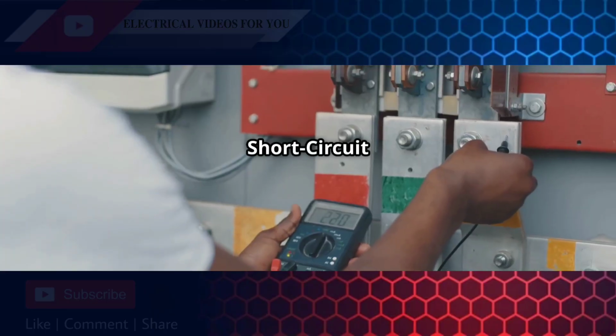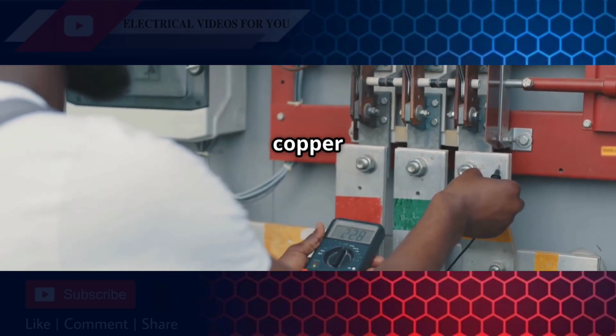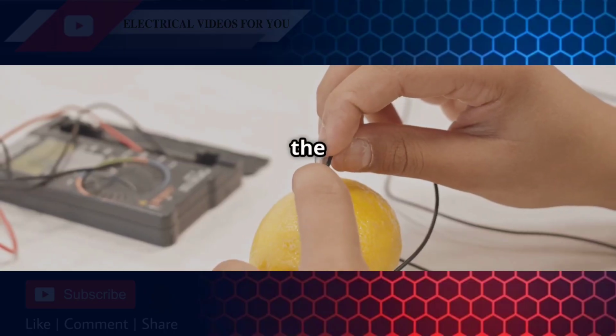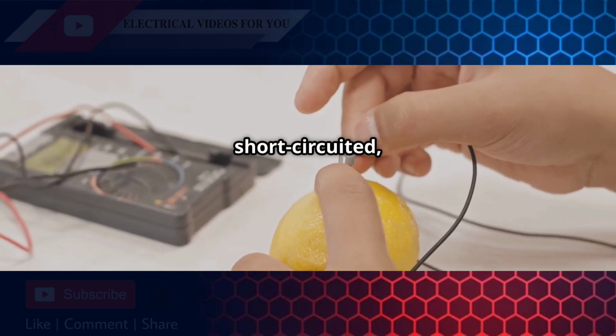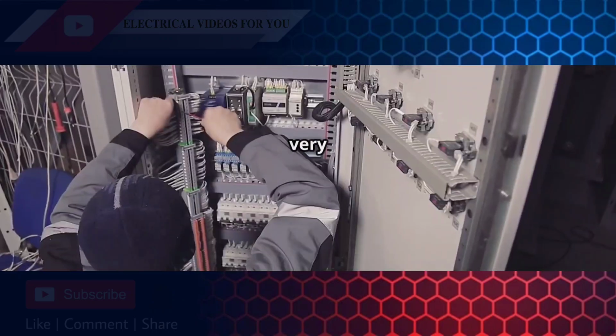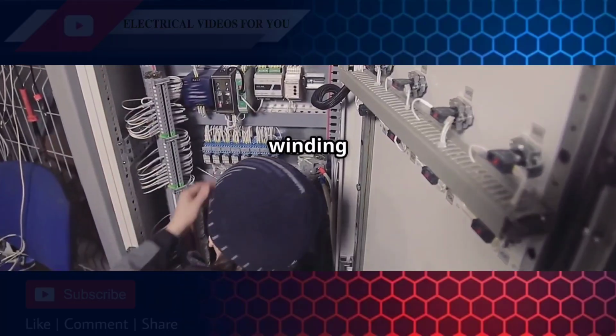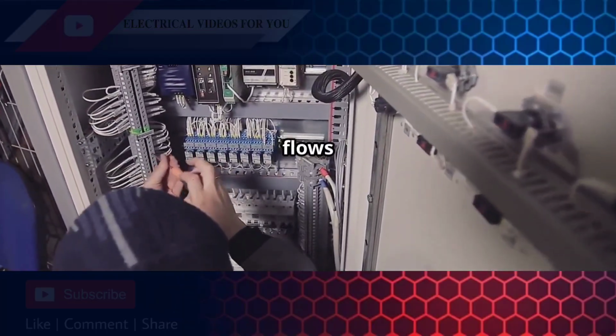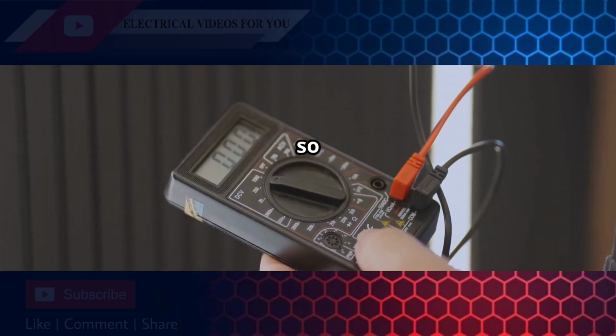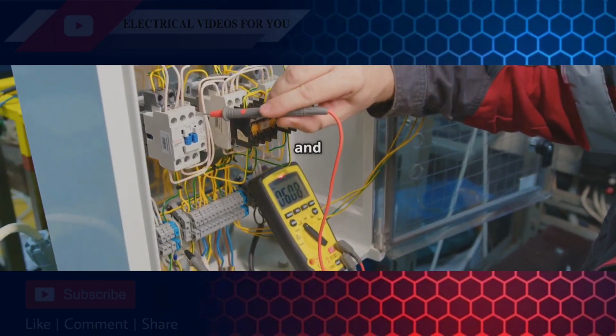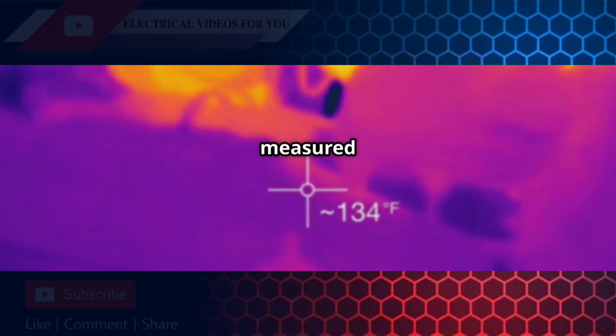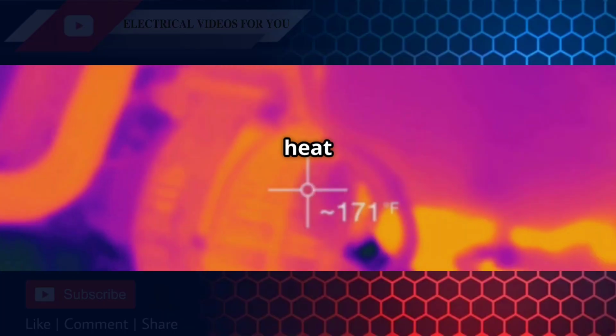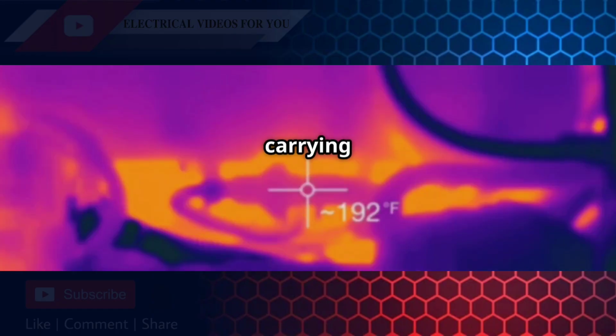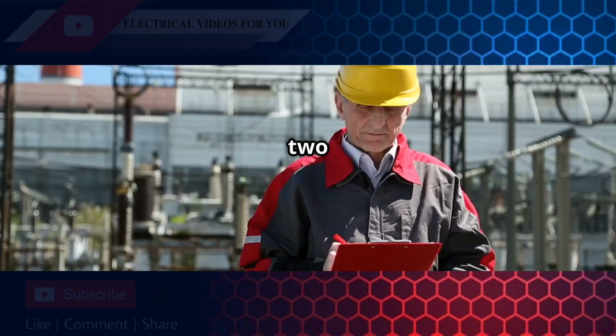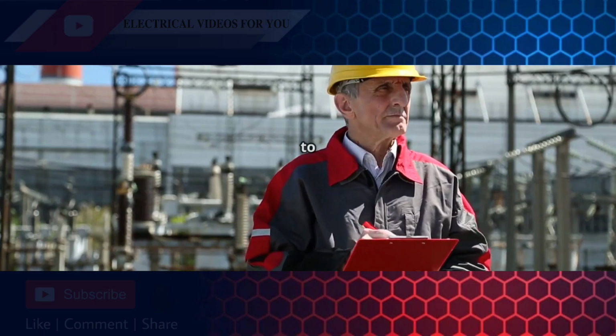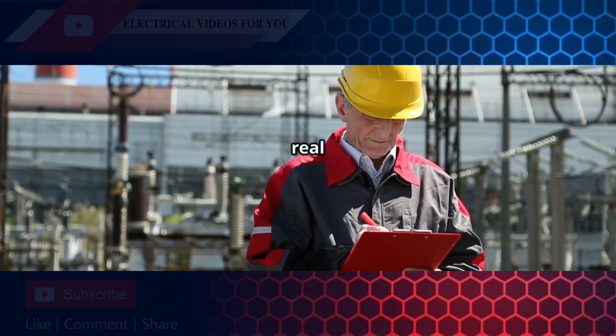The short circuit test, on the other hand, helps us find the copper losses. For this test, the secondary winding is intentionally short-circuited, connected with a thick wire, and a very low voltage is applied to the primary winding until the full, rated current flows through it. Because the voltage is so low, the iron losses are tiny and can be ignored. The power measured in this test is almost entirely the heat loss from the copper windings when they are carrying their maximum current. These two tests give engineers all the data they need to know how efficient the transformer will be in the real world.